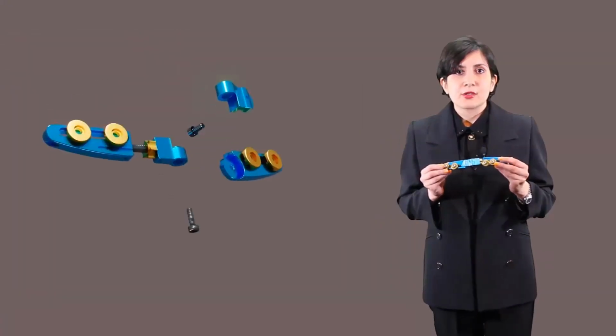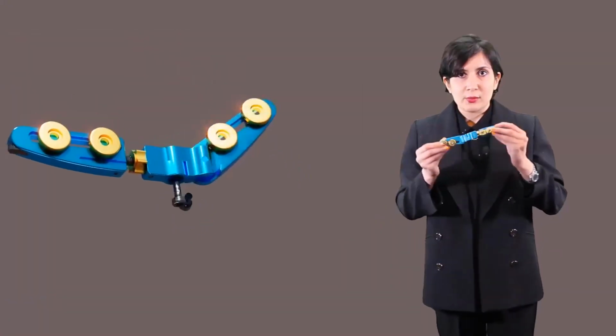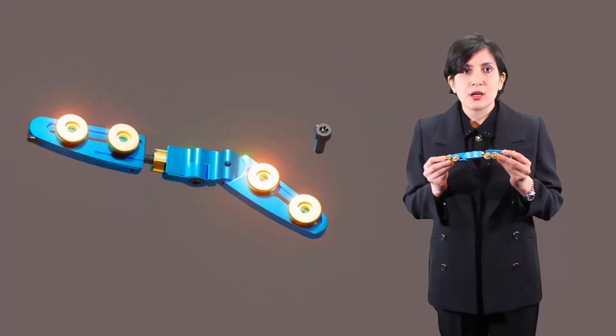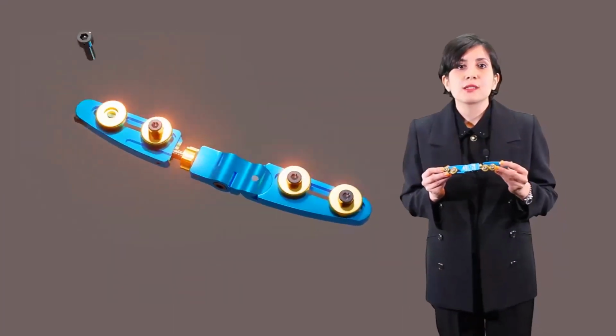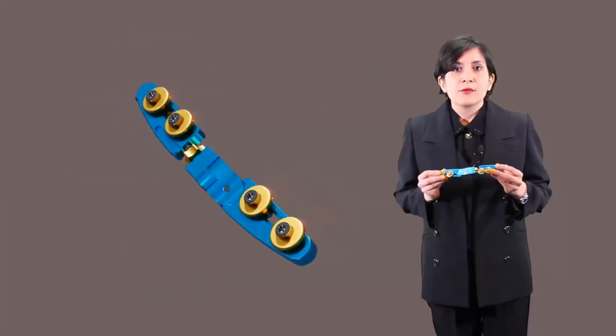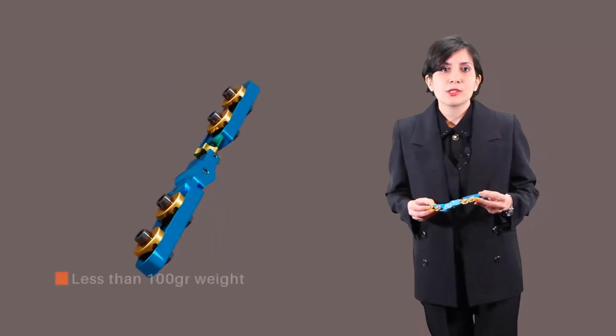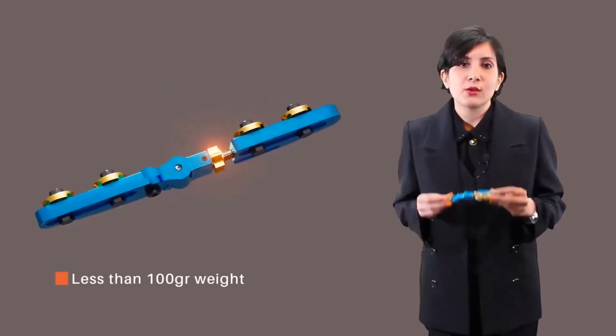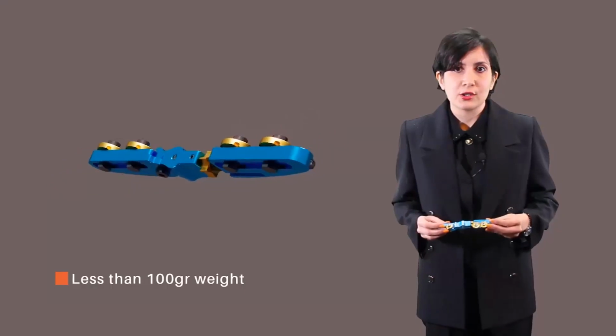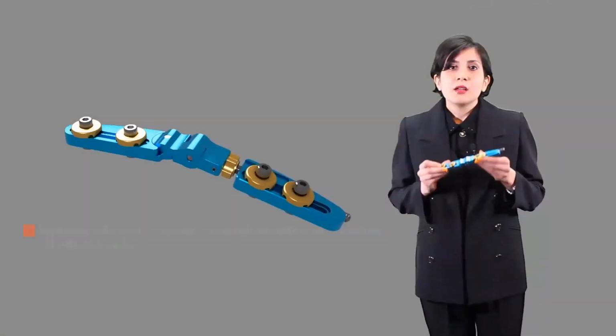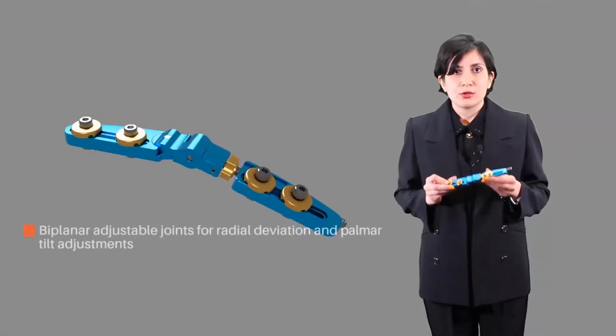This external fixator is composed of two adjustable clamps, a distraction knob, and Schanz pins which can be inserted in multiple directions. Furthermore, the dynamometer controls the distractor force and prevents over-distraction and its complications like stiffness. It has a low profile with less than 100 gram weight.